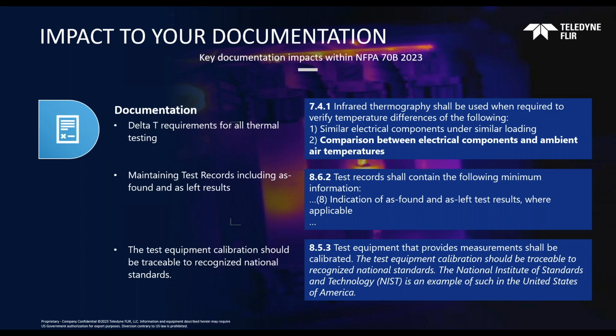And then calibration: test equipment calibration needs to be traceable by recognized national standards. Why is this important? The cameras or any testing equipment, whether you're using a temperature gun, a multimeter, or clamp meter, they need to be calibrated. NIST is a standard example in the United States, and all of our camera solutions that we talk about when it comes to 70B do follow these NIST standards for calibration. It's important that folks understand they need to document those calibration certificates and any data around that.